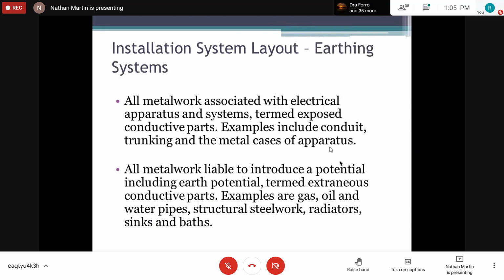Now, the earthing system in our installation. And again, we're just going to look at it briefly, because we could spend a whole semester looking at earthing and the amount of calculations involved, right? All metal work associated with electrical apparatus and systems is termed exposed conductive parts. So we're talking about all metal work, and they are known as exposed conductive parts. Examples include conduit, trunking, and the metal casing of apparatus, right? So we're saying that all of these metal parts should be bonded to earth.